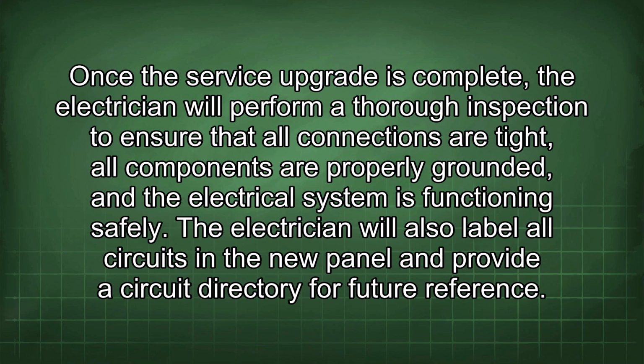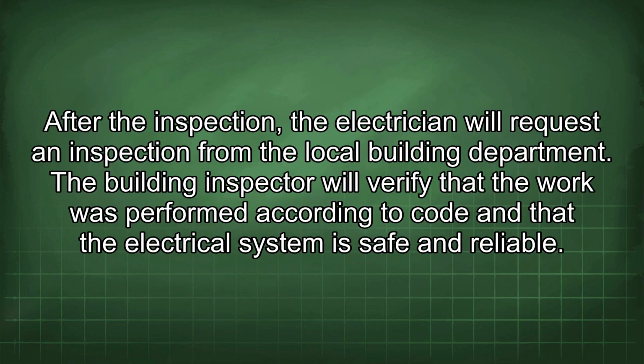Once the service upgrade is complete, the electrician will perform a thorough inspection to ensure that all connections are tight, all components are properly grounded, and the electrical system is functioning safely. The electrician will also label all circuits in the new panel and provide a circuit directory for future reference. After the inspection, the electrician will request an inspection from the local building department. The building inspector will verify that the work was performed according to code and that the electrical system is safe and reliable.